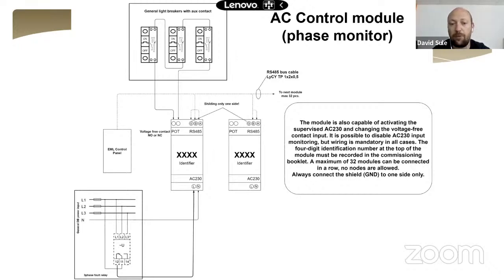And for the communication, we have to give AC230 to this module. When an AC power failure happens, this module can send the information back to the main panel with battery mode, because there is a battery inside. If any communication problem happens with the AC control unit, we can set up communication error group settings for this module. So if we cut the communication cable, after 1 minute the programmed groups of the light will turn on automatically when the panel can't find the AC control communication signal.